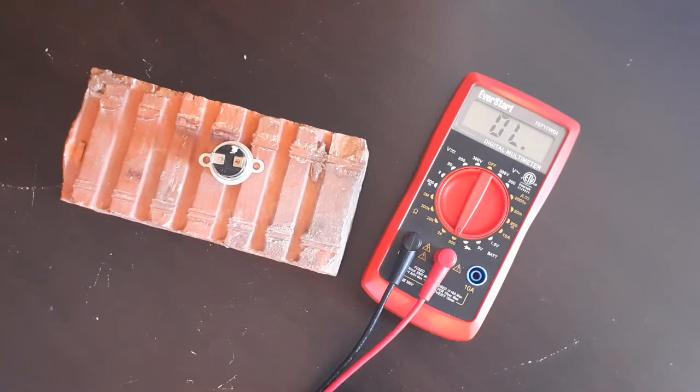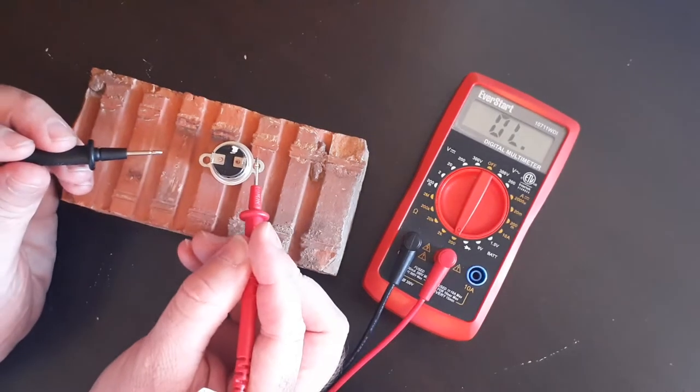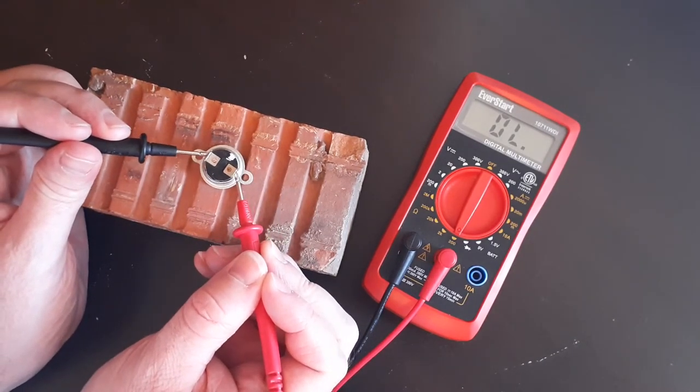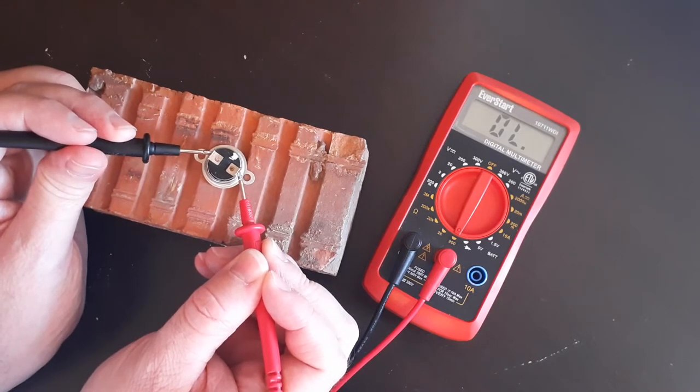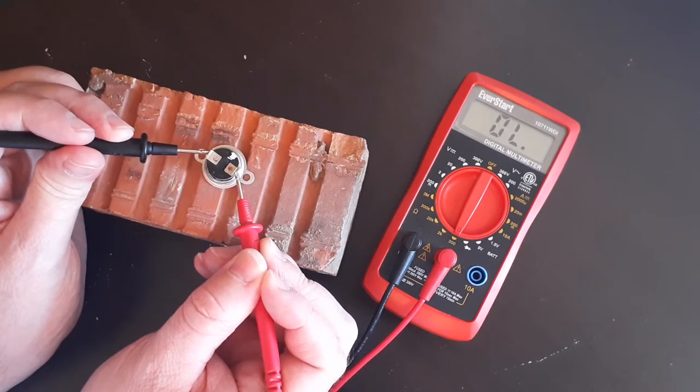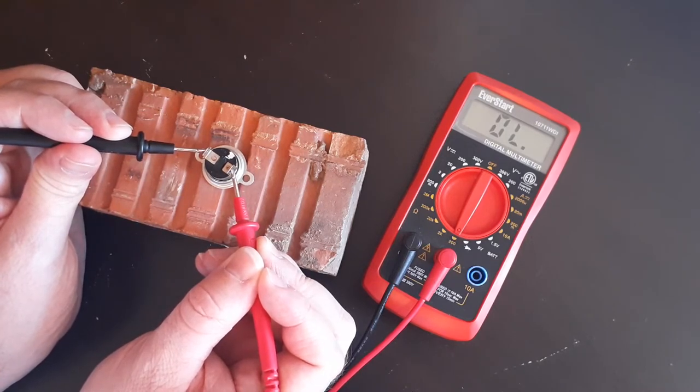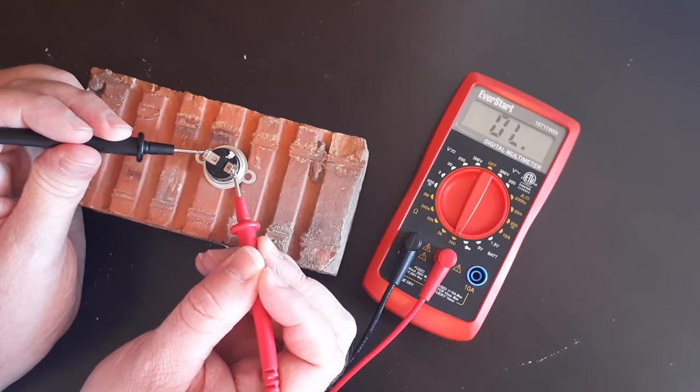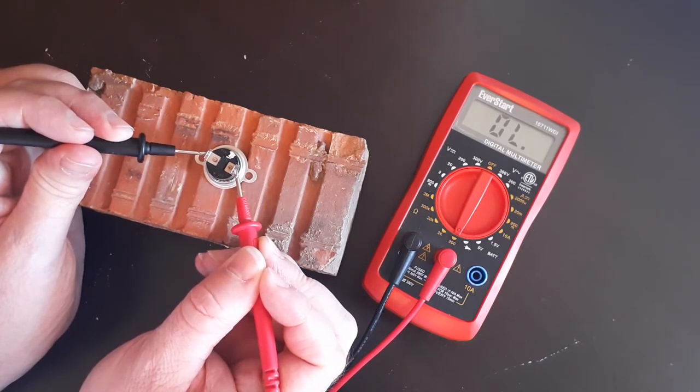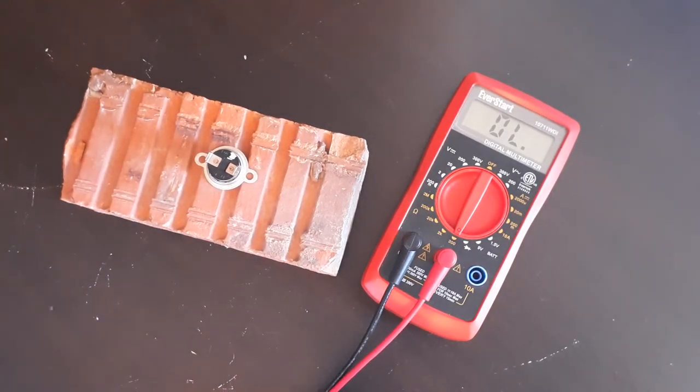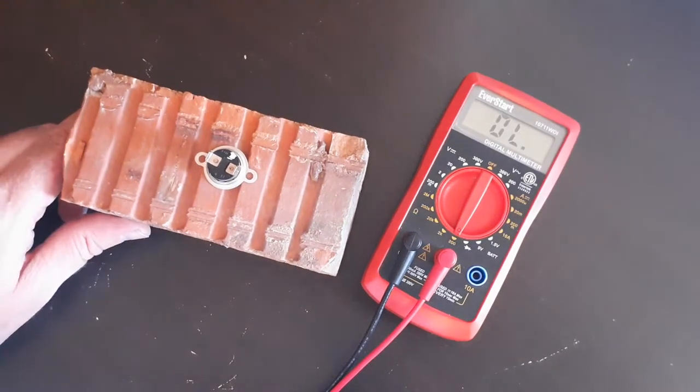There it goes. You saw it jump a little bit. That means that the tabs inside are now open. They are no longer touching each other, so when we touch the leads to this, we do not get a reading. It's still an open line because the leads inside are no longer touching. It's an open line now because we heated it up to the proper degree and the lines inside opened. That's how you do it. So let's go back over it real quick.